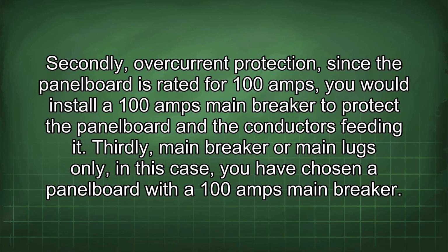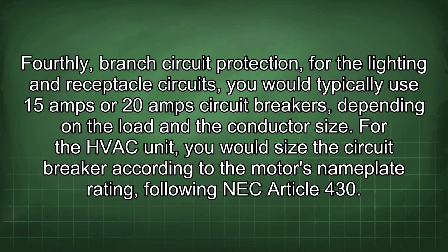Secondly, overcurrent protection. Since the panel board is rated for 100 amps, you would install a 100 amp main breaker to protect the panel board and the conductors feeding it. Thirdly, main breaker or main lugs only. In this case, you have chosen a panel board with a 100 amp main breaker. Fourthly, branch circuit protection. For the lighting and receptacle circuits, you would typically use 15 amp or 20 amp circuit breakers, depending on the load and the conductor size. For the HVAC unit, you would size the circuit breaker according to the motor's nameplate rating, following NEC Article 430.